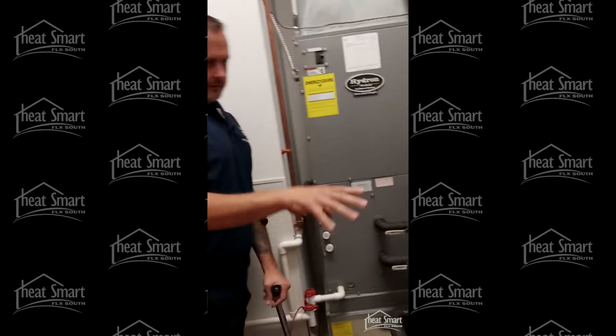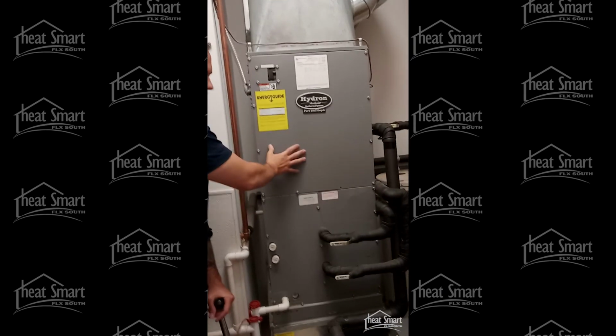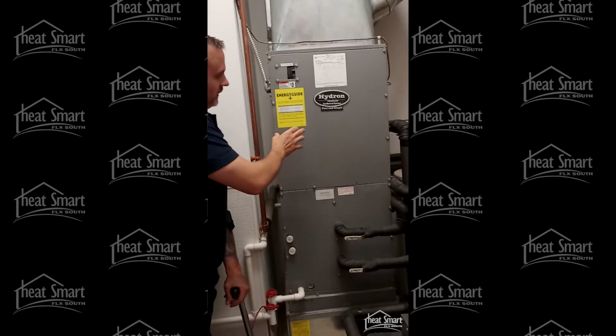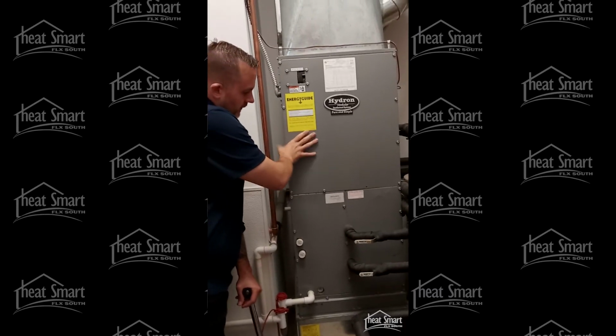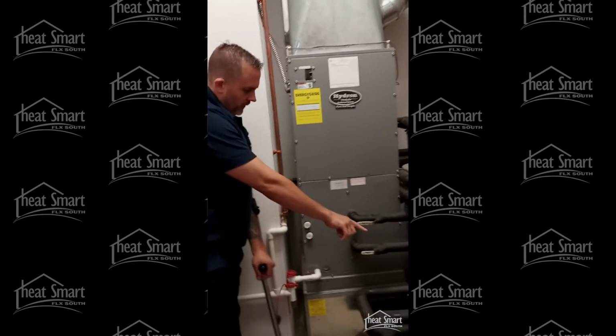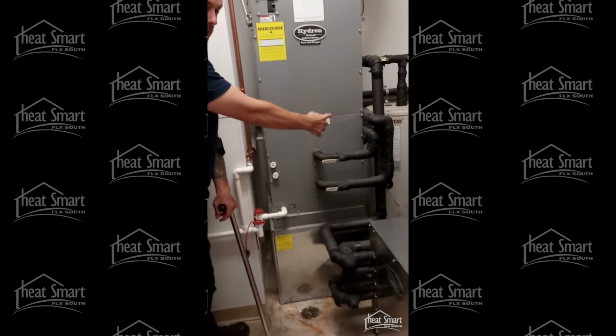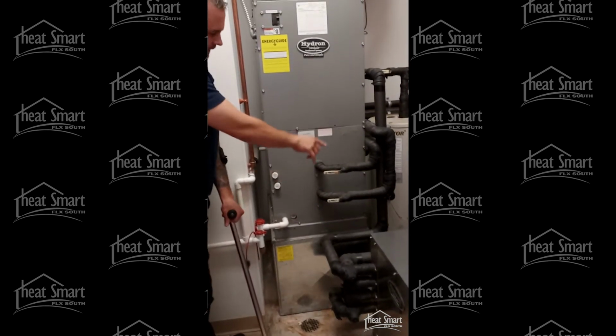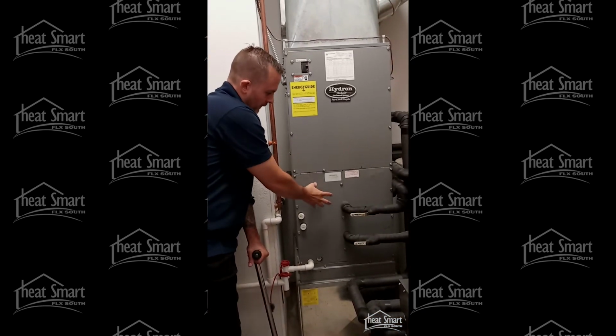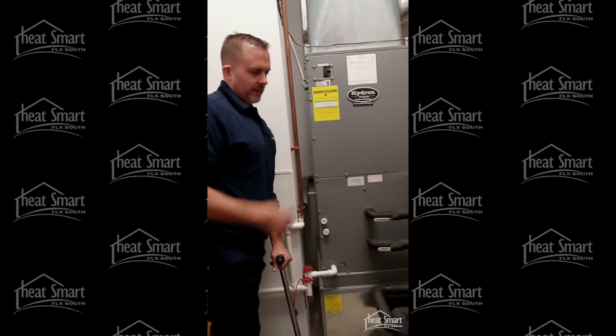So in this situation, you've got heating in the floor, and then air conditioning with a forced air system. This big system is a Hydron model in this case. That's the air conditioning, a hot water, chilled water fan coil. When in cooling mode, you're cooling the water. That tank is now cold, not warm anymore, and that circulates the water through here, and there's a coil inside where the heat transfer happens.